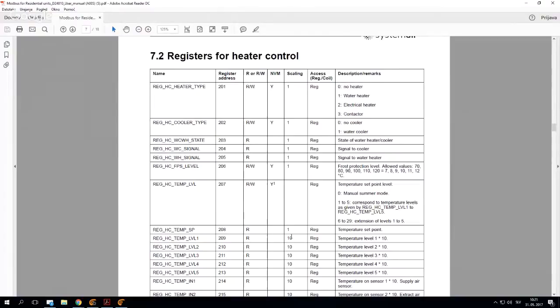It gets a little bit more complicated once we get to temperatures. Temperatures are very important using these kind of devices. You can see that we have a temperature set point here, address is 208. We all know that temperatures usually contain a decimal point. In this case, the integer is not going to be a correct device to use.